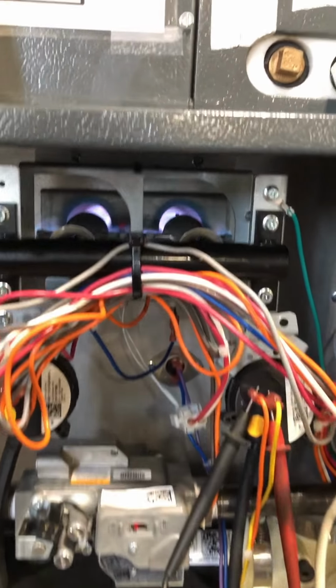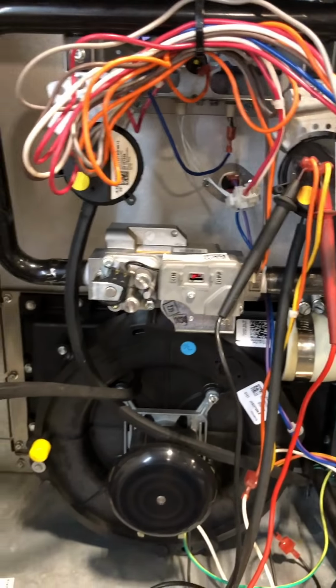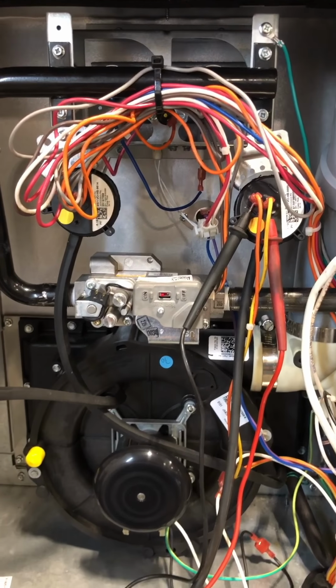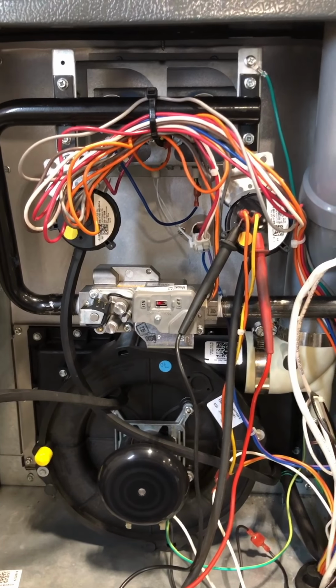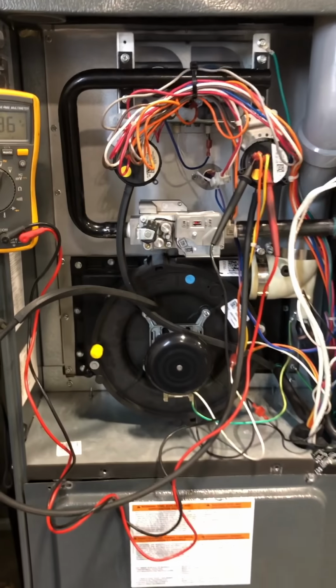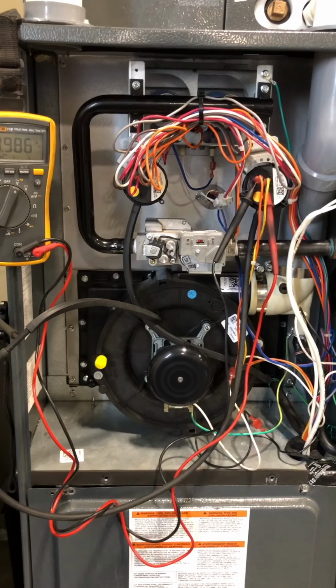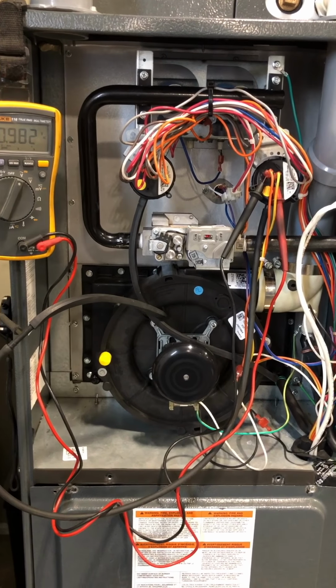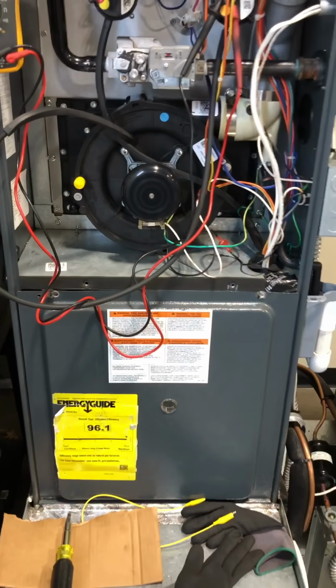Board is satisfied with the flame sense that we're getting. It's keeping the gas valve on. Blower motor will start up after the heat exchanger gets to a certain temperature. Sequence of operation. And there goes the blower motor.